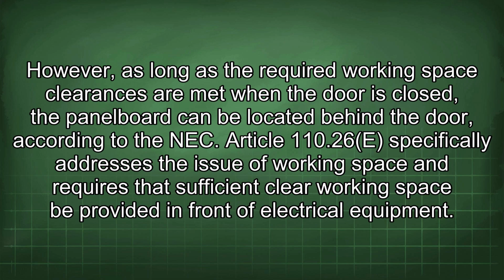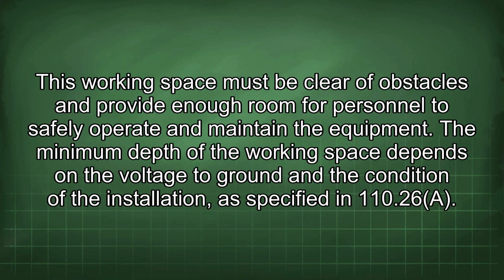Article 110.26(E) specifically addresses the issue of working space and requires that sufficient clear working space be provided in front of electrical equipment. This working space must be clear of obstacles and provide enough room for personnel to safely operate and maintain the equipment. The minimum depth of the working space depends on the voltage to ground and the condition of the installation, as specified in 110.26a.